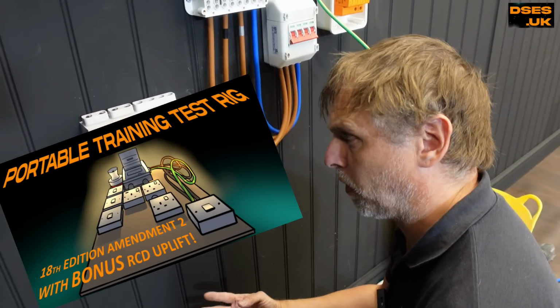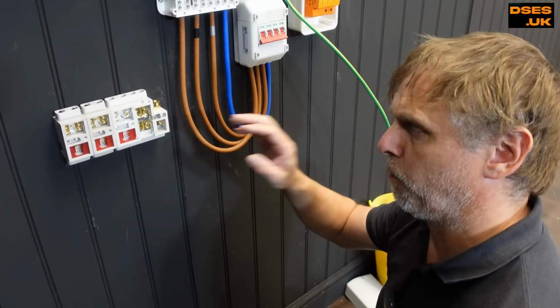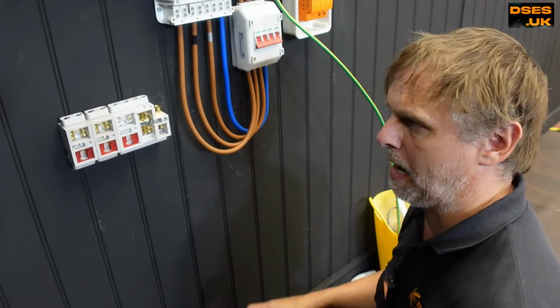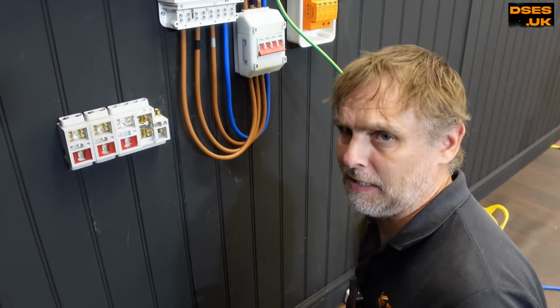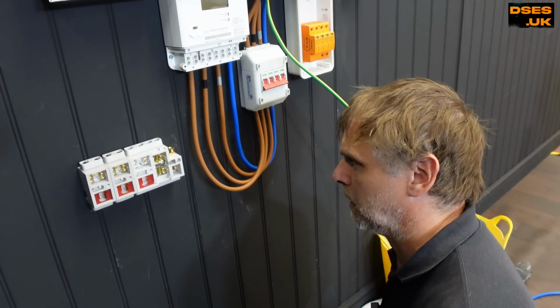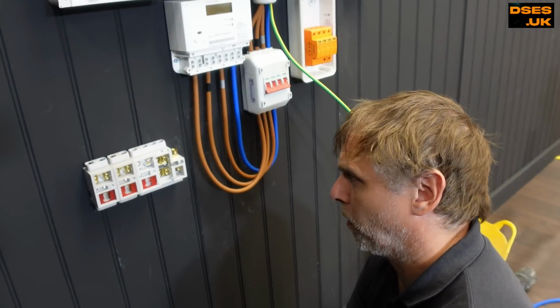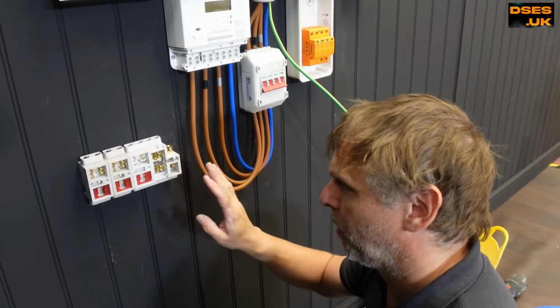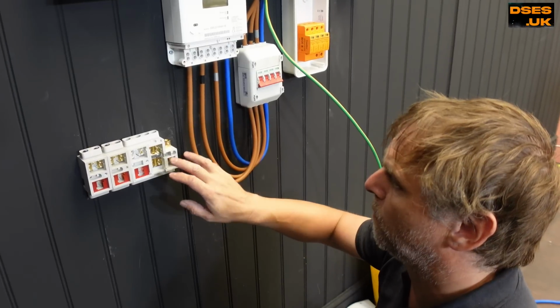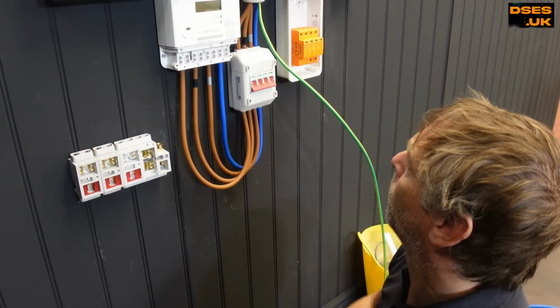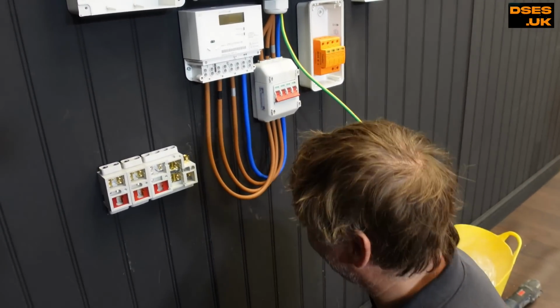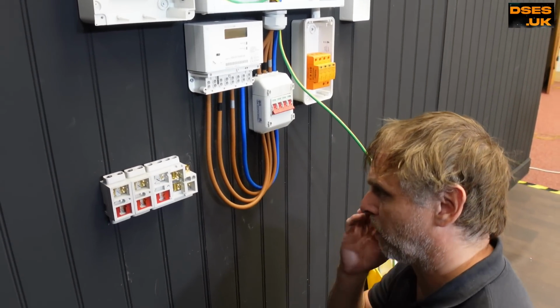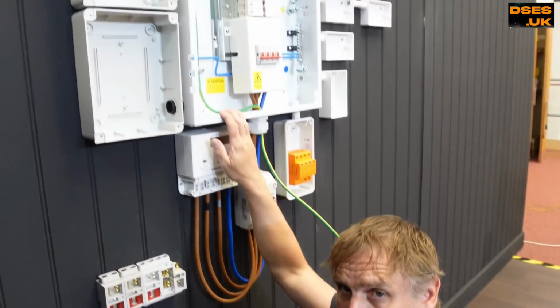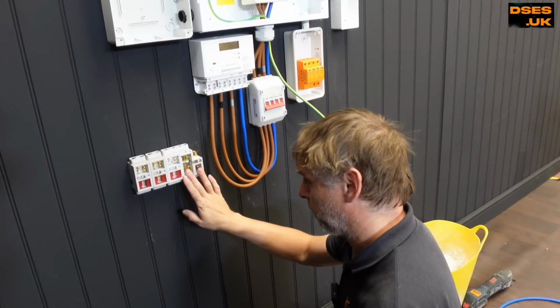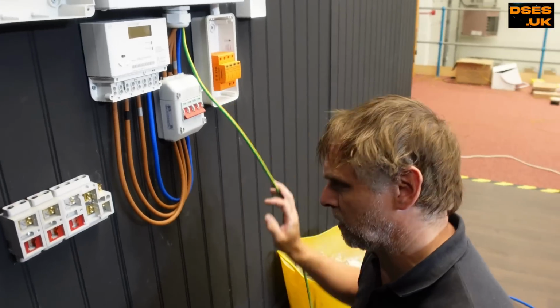I'm not going to do that here. On the portable training test rig video I did that. I got the supply, which is just a 2-core cable, line and neutral, and linked the neutral to the earth. The reason for that was so you could plug the portable training test rig in on an RCD protected circuit and do RCD tests on the rig without tripping the upfront RCD. Here we're running off a breaker, not an upfront RCD, so I can keep the neutral and earth separate, which is best really, because if you link them here there's the potential for the metalwork to go live in the event of a fault. You've got to be very careful how you're using it. Somewhere not under my direct supervision, we want to make sure the earth stuff remains actually earthed, so I'm keeping them separate, but we must make sure we're not on an RCD supply up front, which we're not, it's a 32 amp circuit.